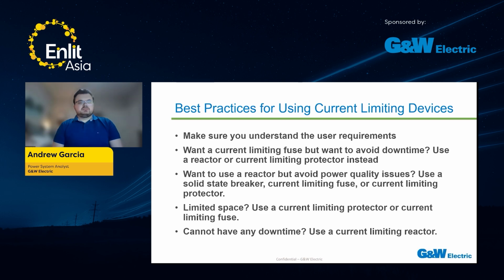All right, so some more of these best practices. Make sure you understand the user requirements before doing this, so you don't end up making a mistake if the user requires different material than what you're using. Do you want to use a current limiting fuse but avoid downtime? Say the customer doesn't want any downtime. You would want to use a reactor or a current limiting protector instead, because the reactor would just passively keep operating and would have no downtime. The current limiting protector can be programmed electronically to only trigger when you absolutely need it.